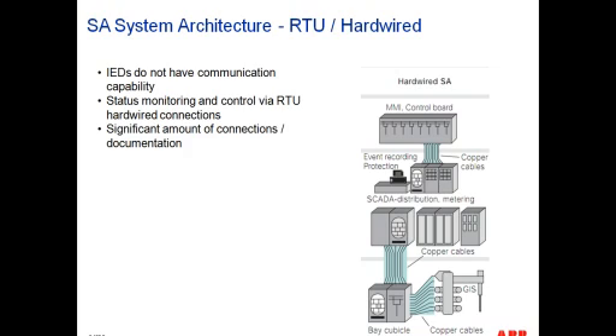And what we would typically find is that, and there are a lot of substations that are somewhat deployed in this same way today, you would have your circuit breakers, you would have all the copper wire from your circuit breakers going into a panel, and then from there you would have more copper wire that will connect to the protective relays. And then you would have essentially a separate system in the form of a remote terminal unit that would monitor some of the quantities of interest coming from the switchgear, such as current, voltage, and position of breakers. You would have connection to the close coils and trip coils of your breakers or motor-operated disconnects to be able to operate your substation that way.